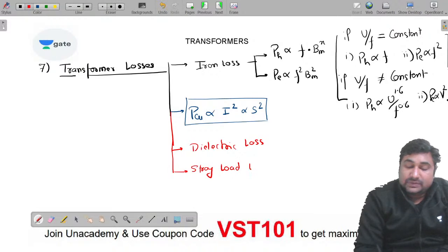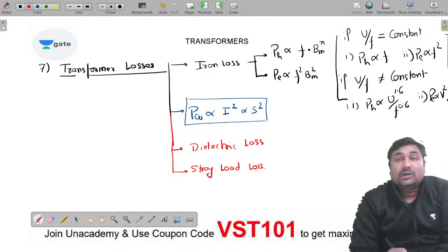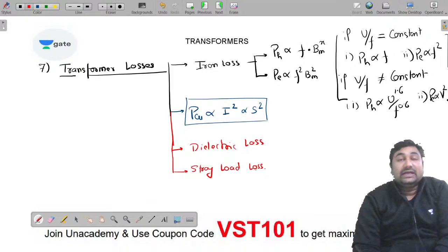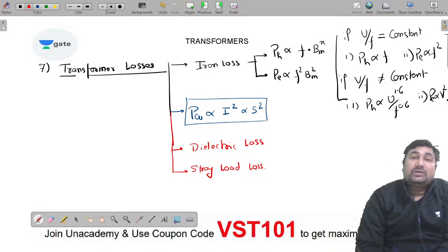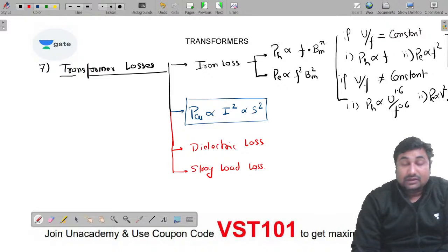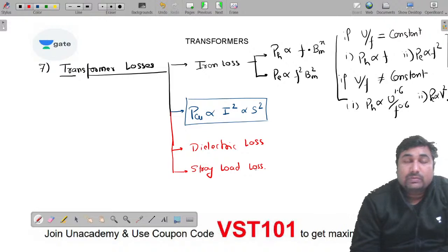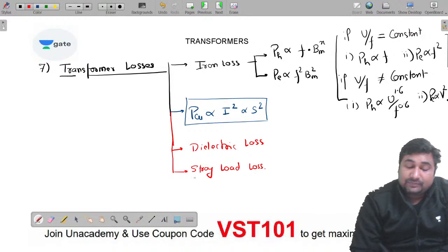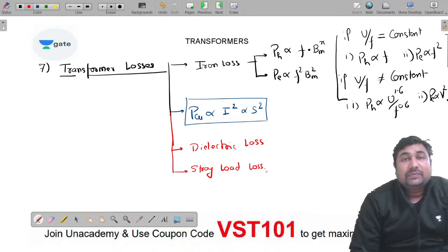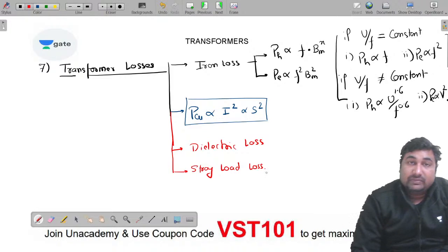Stray load loss is basically a load dependent loss. This loss occurs because of the leakage field. The leakage field creates an eddy current loss in the conductors, tank, channels, and other iron materials other than the core, which are responsible for stray load loss. Leakage field depends upon the load current, so always remember stray load loss is dependent upon the load.